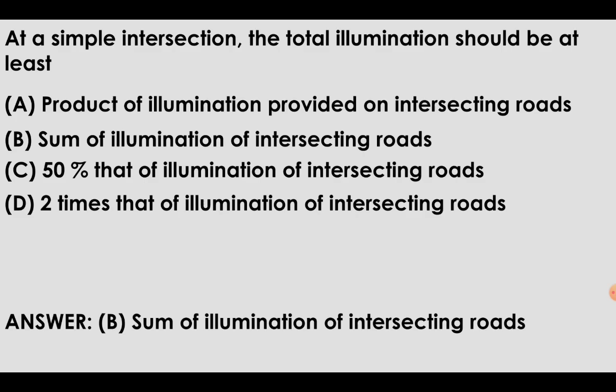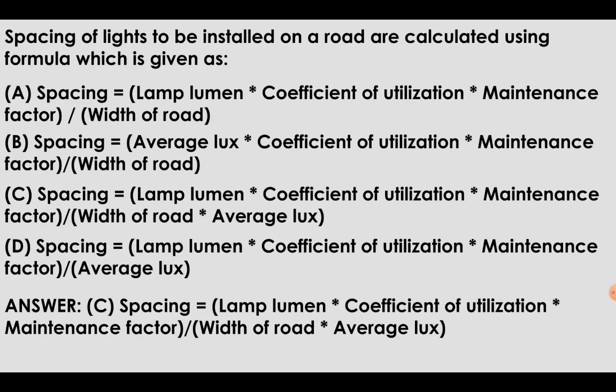Then the spacing of lights to be installed on a road is calculated by using the formula: spacing is equal to lamp lumen into coefficient of utilization into maintenance factor, whole divided by width of road into average lux.